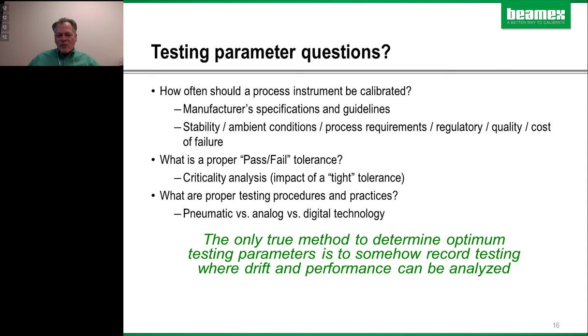So another parameter you have to figure out: what is the pass-fail tolerance? You might do what's called a criticality analysis, and I add this little comment here. So you guys that were doing, 6-7% of you were doing tighter than 0.5%. That costs you in a lot of ways. You need to have more accurate test equipment. You need to have good gear to make those measurements, and you might need to go out more often if there's some stability or drift issues with that given instrument, in order to be confident that you're making that tight tolerance. So that's a message for management, that when you ask your tech to do something to 0.25%, just know that you're asking a lot.